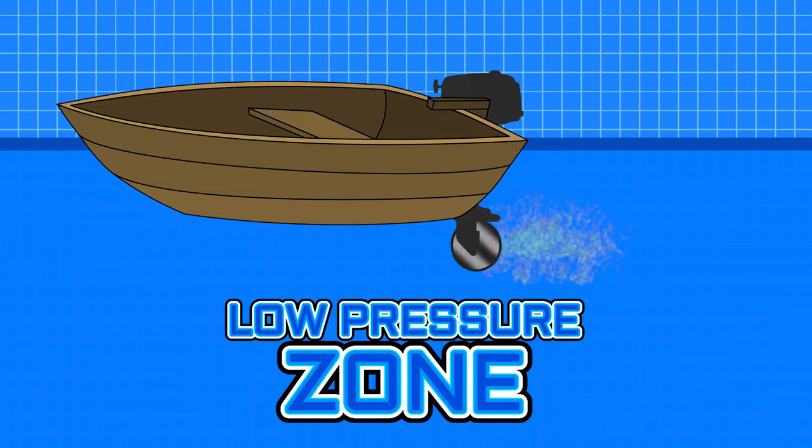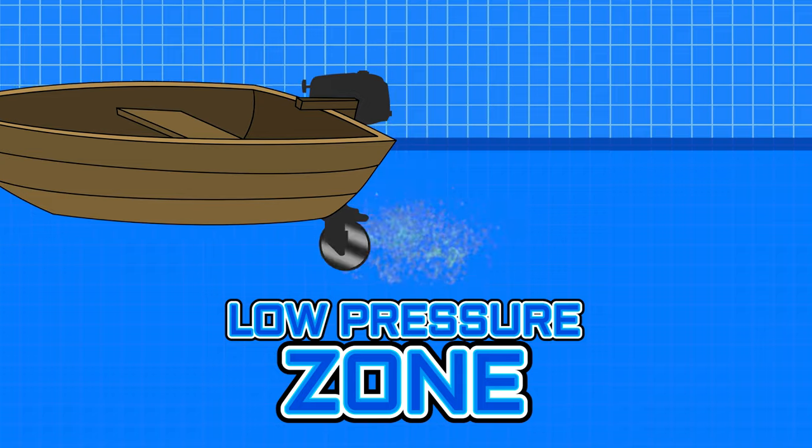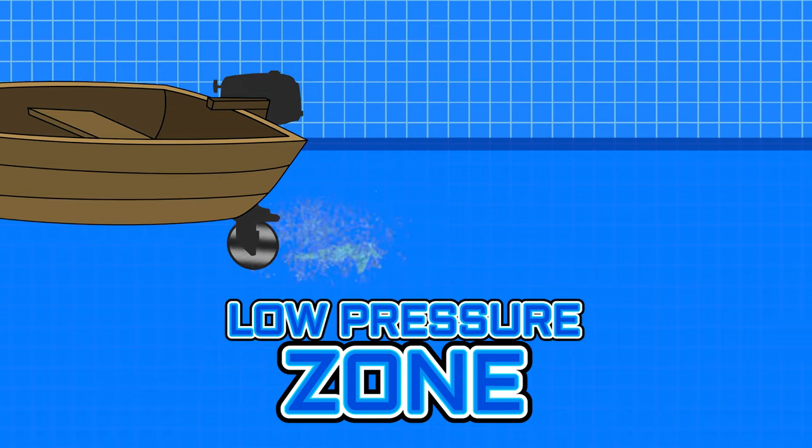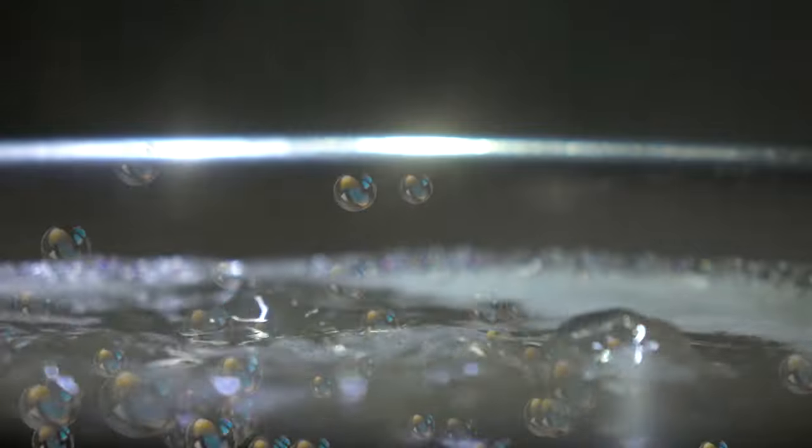This creates a low pressure zone on the trailing side of the propeller. This low pressure zone causes the water to boil at ambient temperatures of the fluid, so small steam bubbles are created due to boiling. These steam bubbles then implode due to the surrounding pressure of the water.